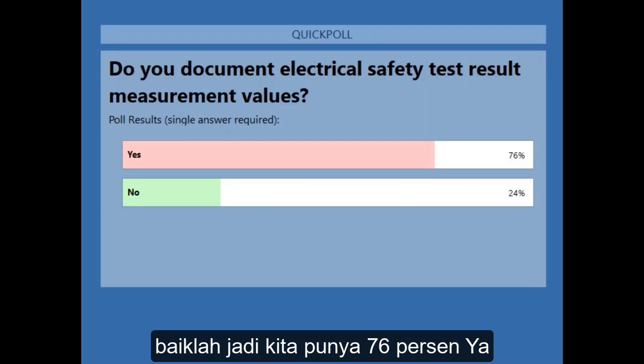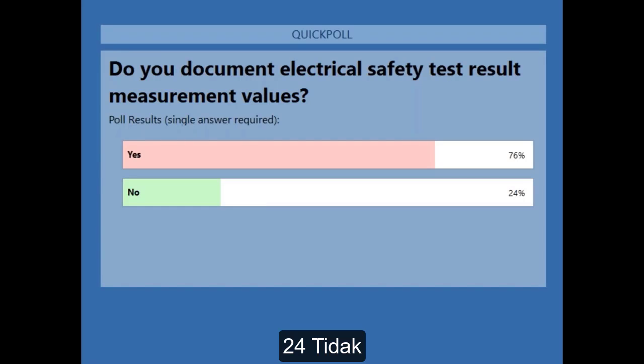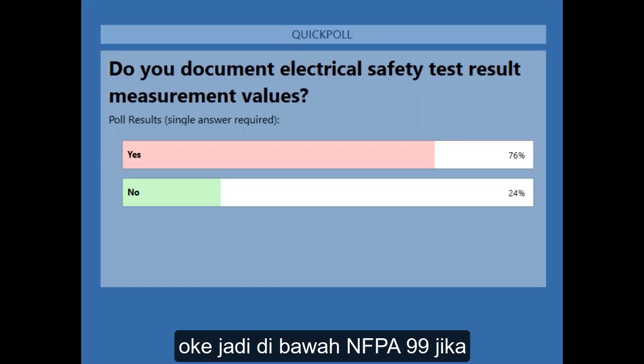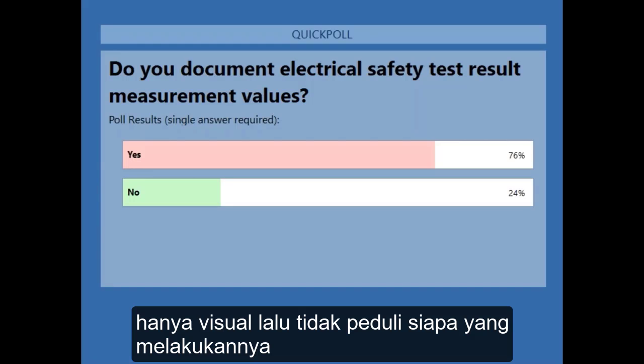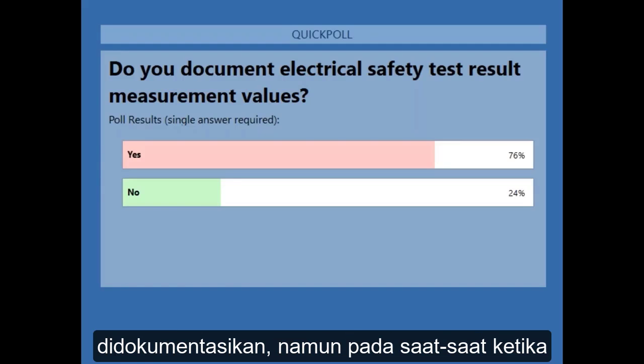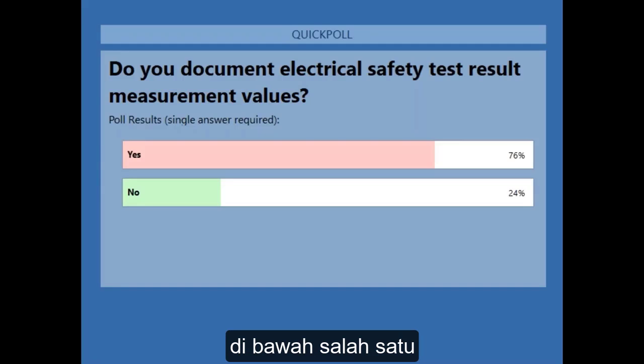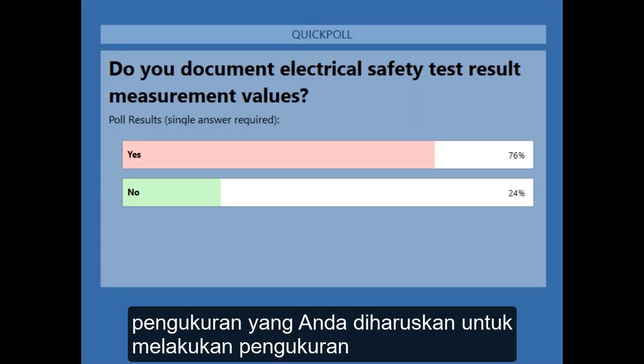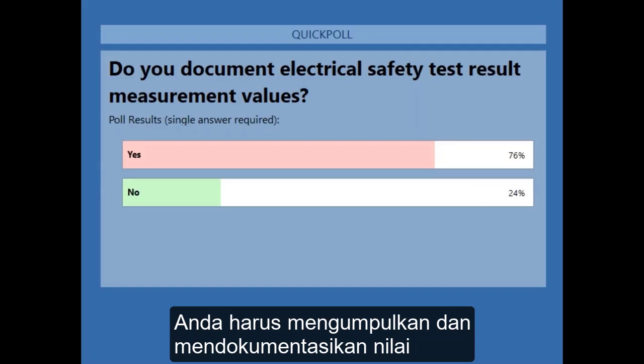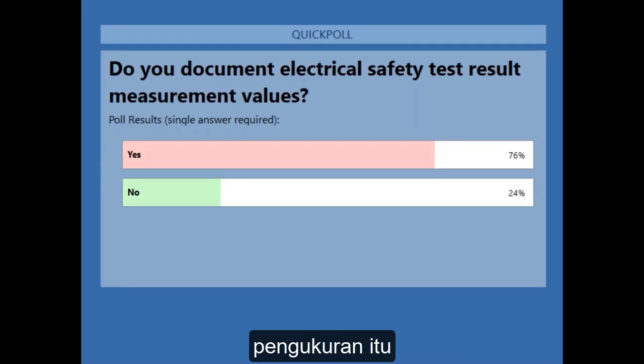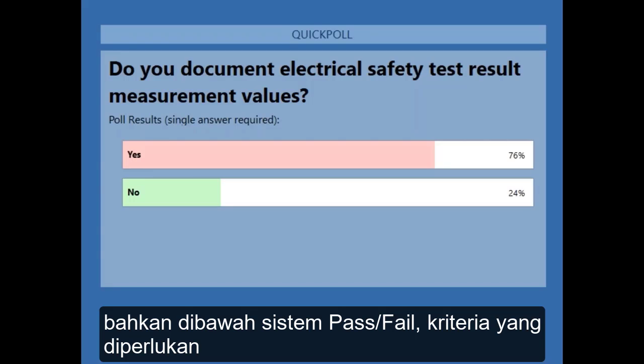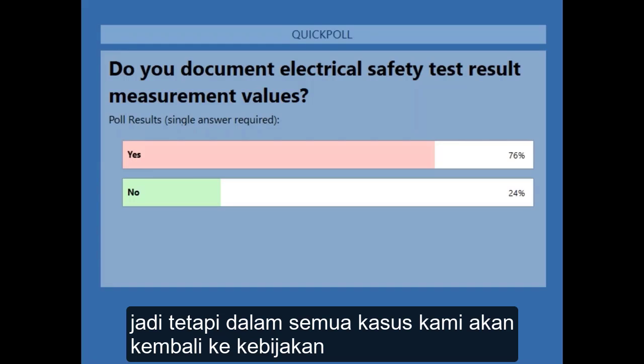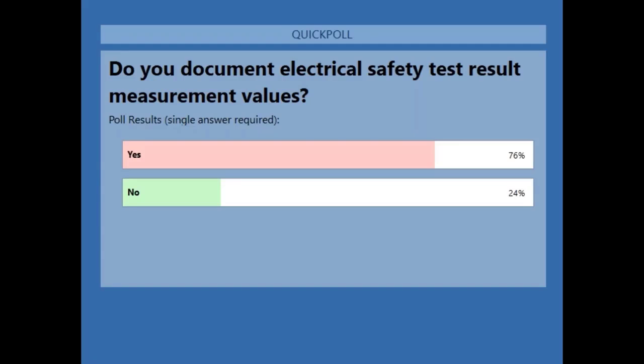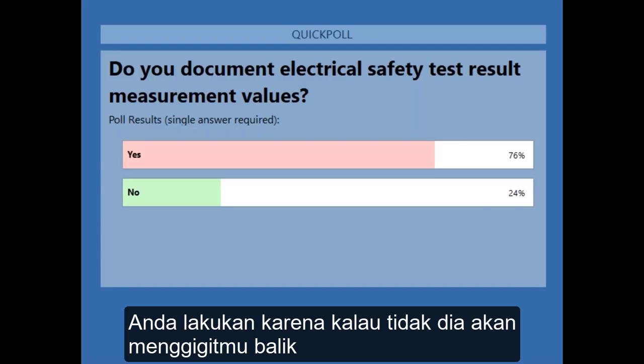All right, so we have 76% yes, 24% no. Okay, well, under NFPA 99, if the testing is just visual, no matter who's doing it, then there are no measurement values to document. However, at any other time, under any of the regulatory standards, that you're required to do a measurement, you should be collecting and documenting the value of that measurement, even under pass-fail criteria. But in all cases, we'll go back to policy again. Do what your policy says you're going to do, because otherwise it's going to bite you on audit trail.